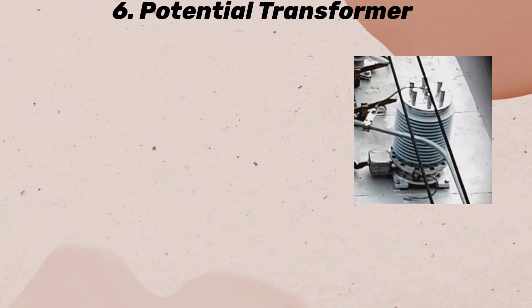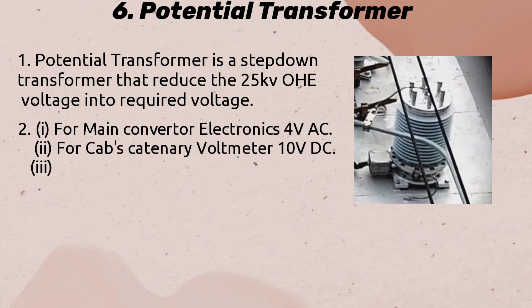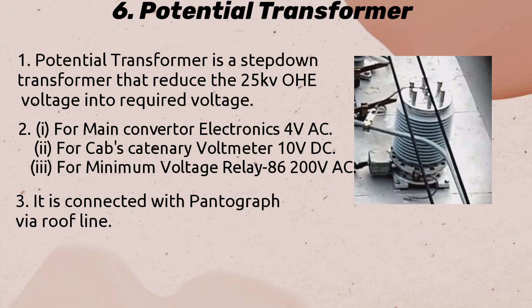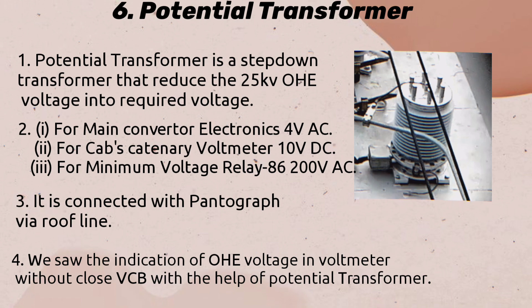Potential Transformer: The potential transformer is a step-down transformer that reduces the 25 kV OHE voltage into required voltage — for the main converter electronics: 4 volts AC; for cab catenary voltmeter: 10 volts DC; for minimum voltage relay 86: 200 volts AC. It is connected with the pantograph via roof line. We can see the indication of OHE voltage in the voltmeter without closing the VCB, with the help of the potential transformer.